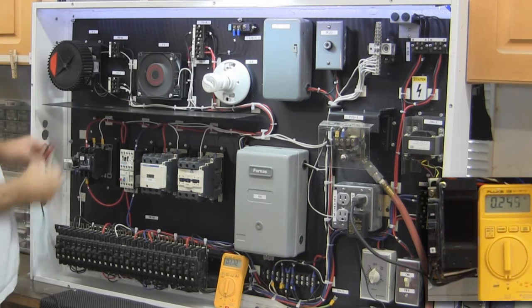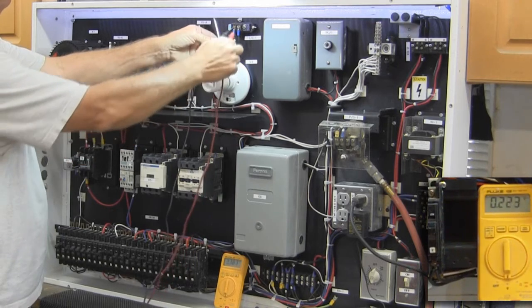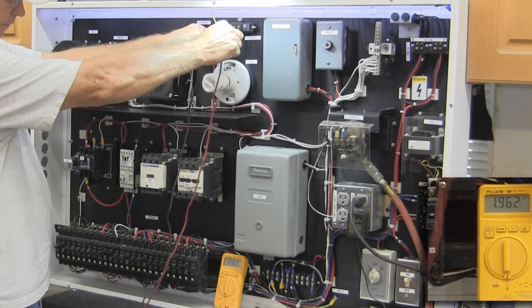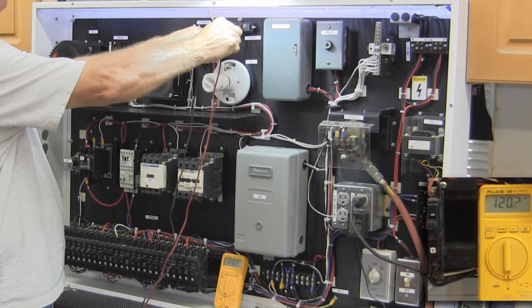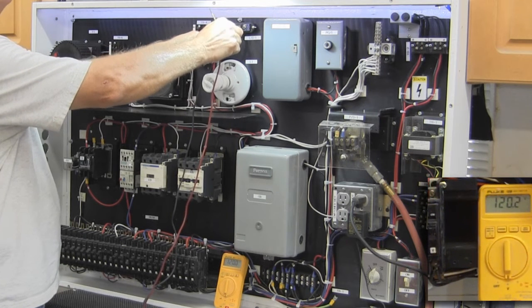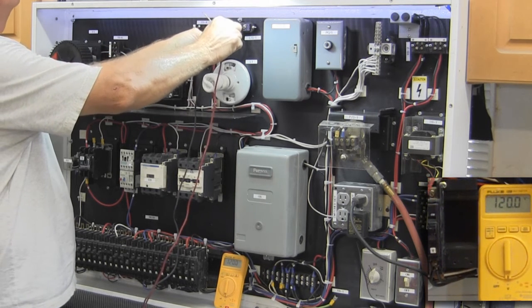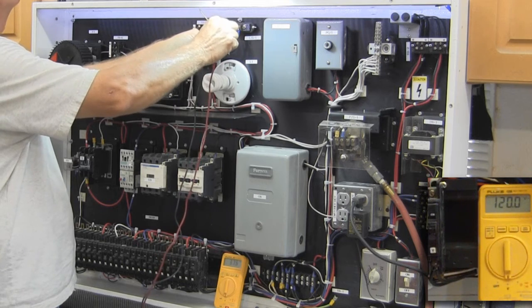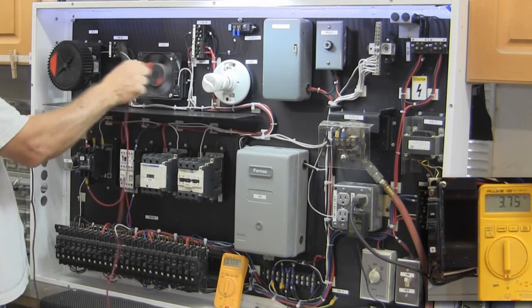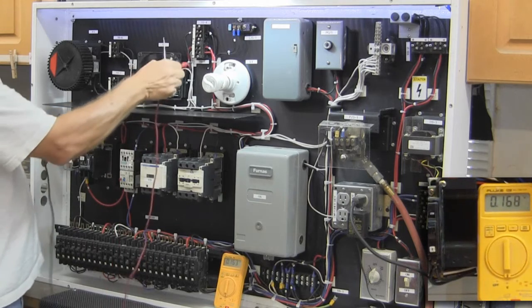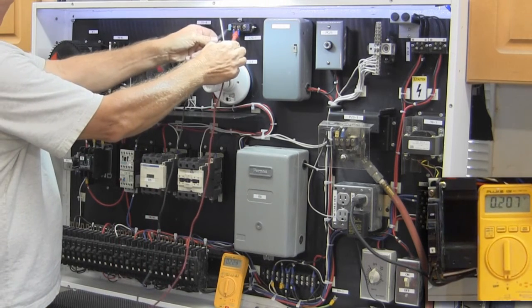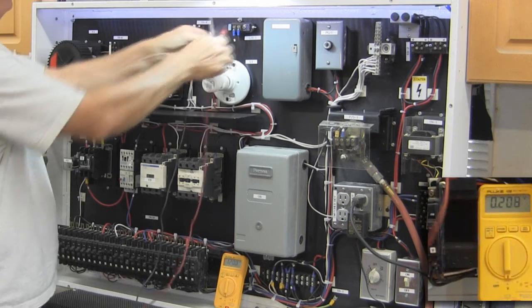Let's cut the power on, and if I go between these two I'm getting 120 volts. The reason for that is I'm getting the power coming in here, but I'm reading through the neutral on this fan motor. So if I were to disconnect that neutral and test between these two, I wouldn't get anything.